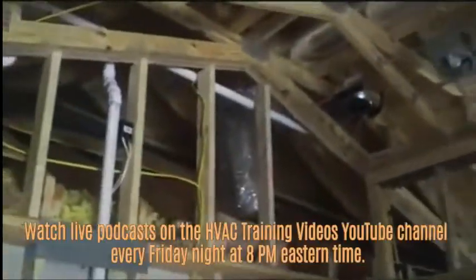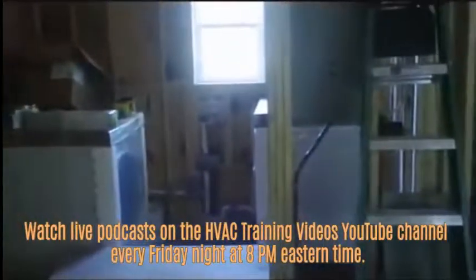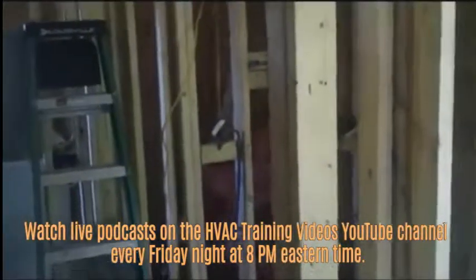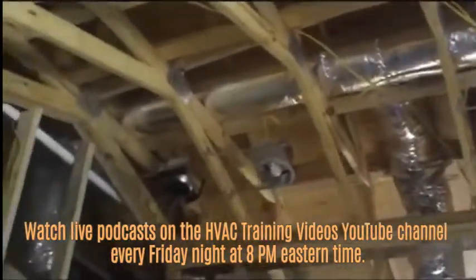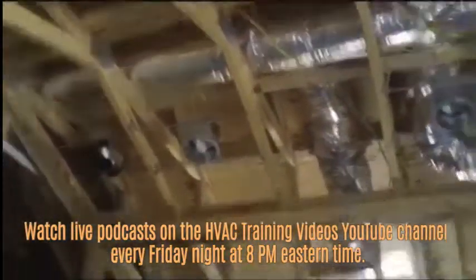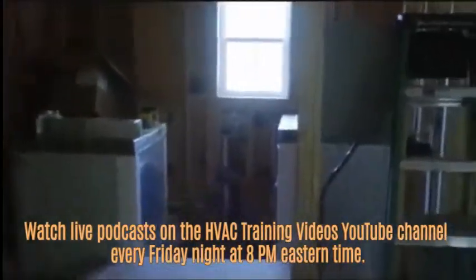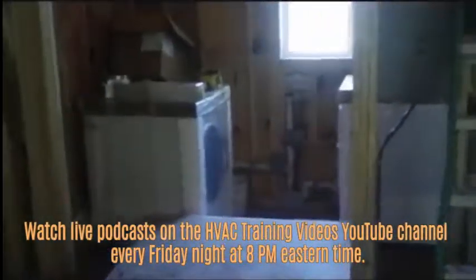Trying to deliver about 200 to 250 CFM of air into this area, servicing just a master bath, laundry room, closet, jacuzzi, and walk-in shower. Wanted to get enough air, which is why we went with a 9-inch instead of an 8-inch branch, since the laundry is right there and it vents for hour-long periods, possibly in the middle of the day.